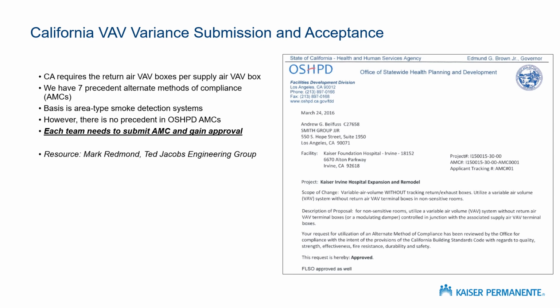So let's talk about VAV in the state of California. If you're outside of California, you can skip this slide. But for those of us in California, I'm sure most of us know, California requires a return air VAV box for every supply air VAV box. And in economic terms, that has effectively acted as a ban or a barrier to VAV in California hospitals. It kind of doubles the cost of your air distribution system, which frankly is not a good investment.